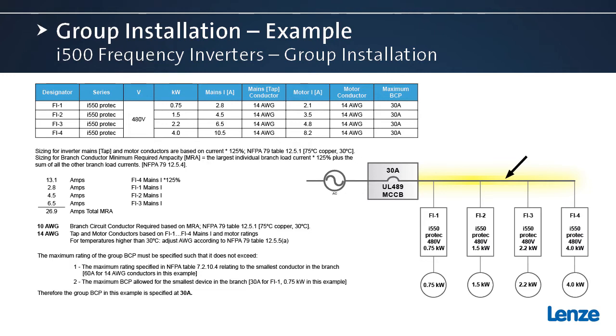We go back to our NFPA table 12.5.1 for 26.9 amps. The result is that we can use a 10 gauge wire. Next, we'll look at the motor conductors. Those are also based on the motor currents in this table using NFPA 79 table 12.5.1. There we result with 14 gauge.